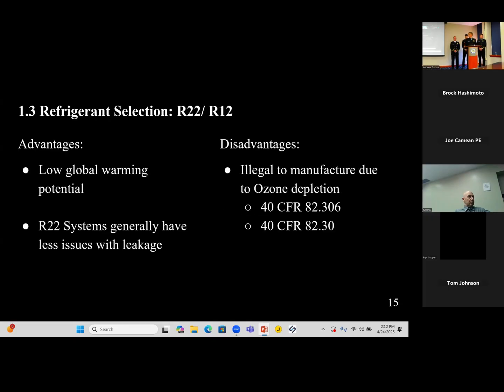Next system we looked at is R22 and R12. Now, this has a low global warming potential, believe it or not. And generally, because the systems are built in a way that's robust, they have less issues with leakage. Now, the unfortunate thing about R22 and R12 is it was made illegal to manufacture back in the 90s. Here are the related CFRs to the ozone depletion and R22 and R12. And for that reason, the prices on it fluctuate a lot and the access to it fluctuates a lot. So for that reason, we're not going to use R22 or R12.